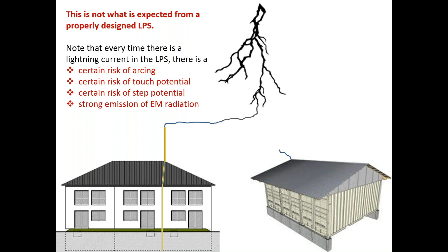So therefore, we always try to make sure that if a lightning step leader is going to attach with our building, then the lightning protection system will interact with that lightning, but not a lightning which would have gone to somebody else's building that I'm going to get into my building. So what you see in this slide is a wrong concept of lightning protection.